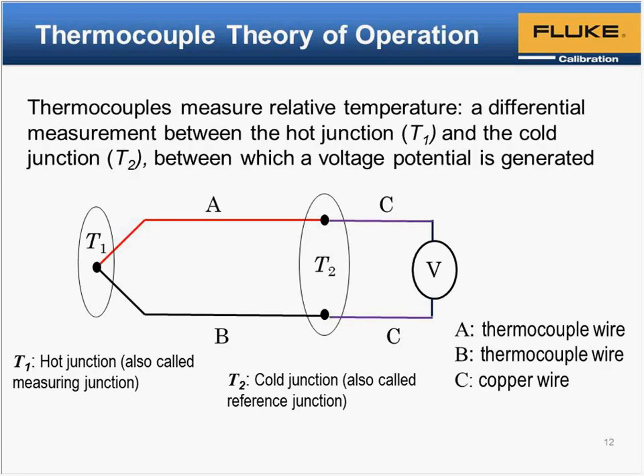And it's probably important to go over the theory of operation. There's a lot of misunderstanding of how thermocouples work. Generally, the thought is that the measurement signal is generated out here at the tip, identified as T1, in this circuit. But in general, you can consider that the temperature that we see on the display of the readout is the difference between T1 and T2. However, even though it's not totally correct, that's generally what's going on, and it works fairly well. That's something else we need to talk about here before we move to the next slide.